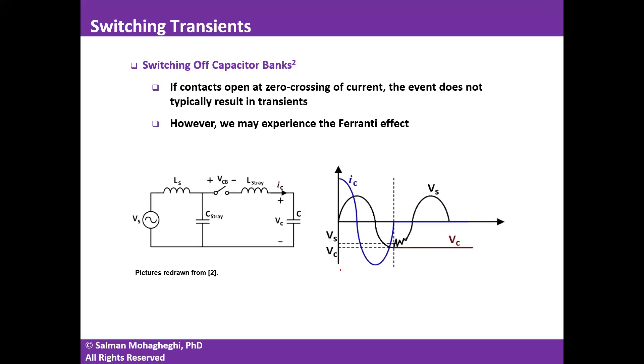What about when we switch off capacitor banks? Usually, because we wait for zero crossing of current, this does not lead to significant transients. However, one interesting phenomenon we may experience is the Ferranti effect. If I have a source V_S connected to a capacitive load, depending on system parameters and how large the inductance is, the voltage on the load side can be larger than the voltage on the source side — this is known as negative voltage regulation.